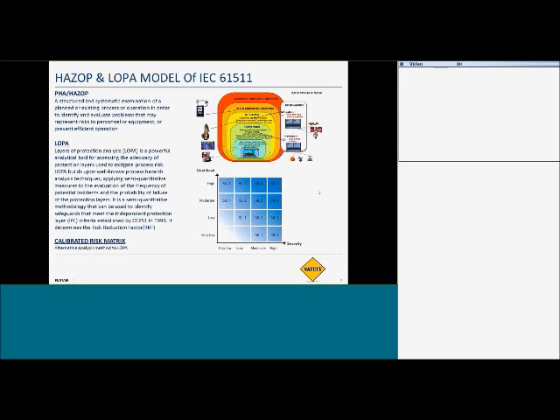So they begin to drill down, first of all, looking at outside the plant, what's the community emergency response for safety? Within the plant, what's the plant emergency response? What are they doing to mitigate hazardous situations within their plant with mechanical mitigation systems and safety instrumented control systems? And then finally, all the way down to basic process control systems. And they just keep drilling down, analyzing what the hazards are and what they are doing to be safe. Within this process, they have a couple different methods for doing statistical analysis of what layers of protection they have. One of these is called LOPA. You see in the middle of this slide, layer of protection analysis, and that's really a deep dive analysis, both quantitative and qualitative, of what safety systems they have in place.